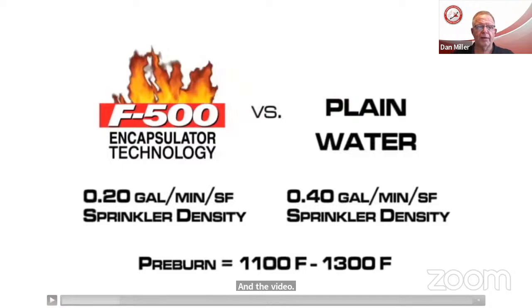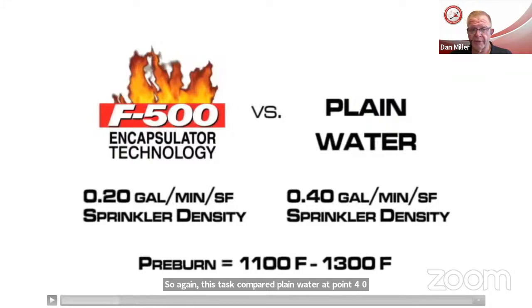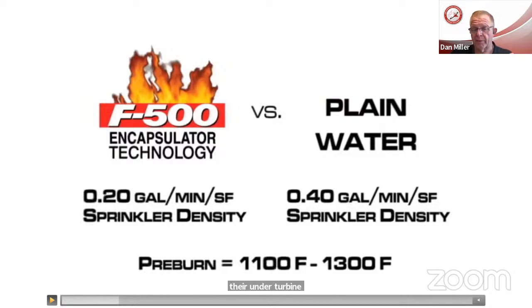So again, this test compared plain water at 0.40 gallons per minute per square foot sprinkler density with F500 3% concentration at a 0.20 gallon per minute per square foot sprinkler density. So half the sprinkler density. 0.20 was also the previously existing sprinkler density of their under turbine lube oil system. Now, this test included a pre-burn time to allow the burning product to reach 1100 to 1300 degrees Fahrenheit. So it got plenty hot, heated up the steel, etc., associated with the fire so that it was reality based.